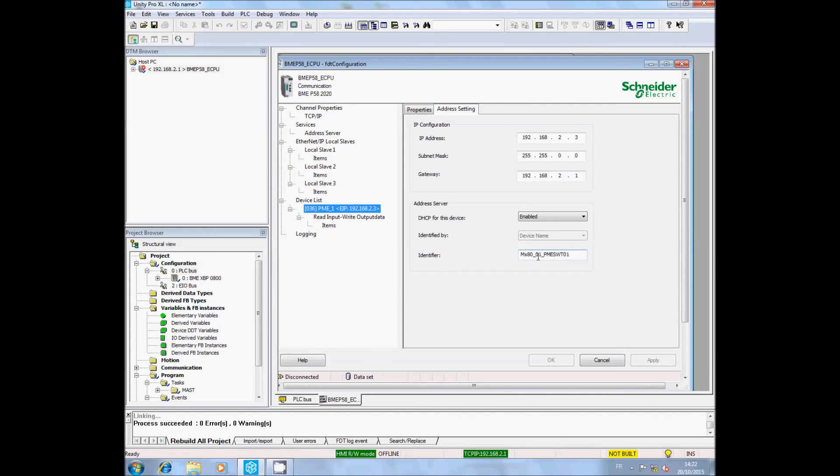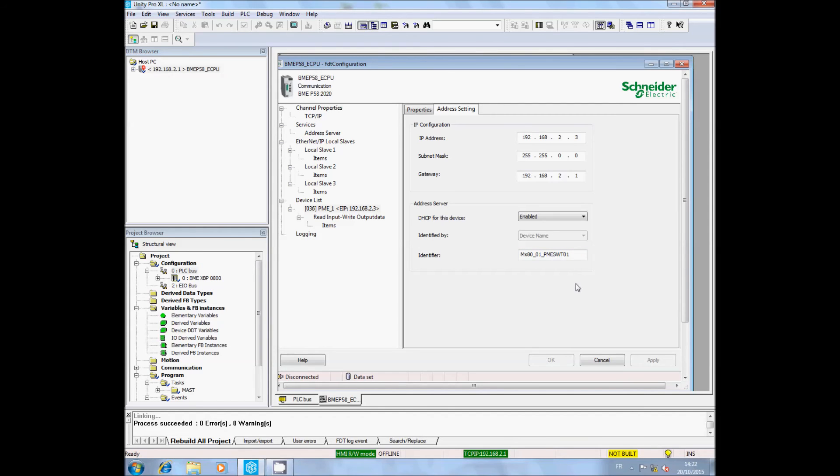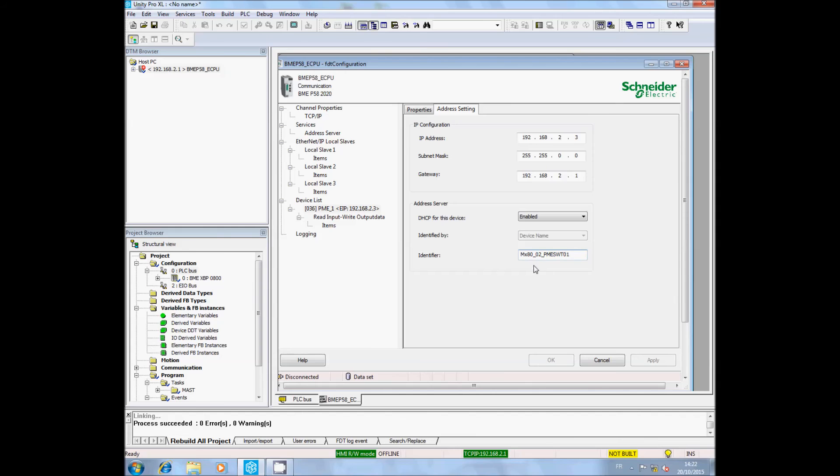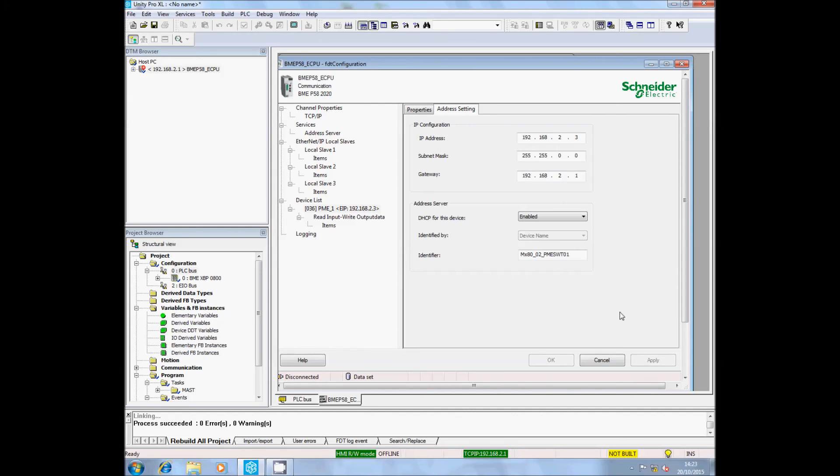We will now change the identifier of the PME SWT. Be extremely careful with this. We will change MX80_01 to MX80 underscore your real slot number. Be very careful - if you mismatch the slot, the PME SWT will never communicate with the M580. In my example, the PME SWT is on slot 2. I apply the modification.